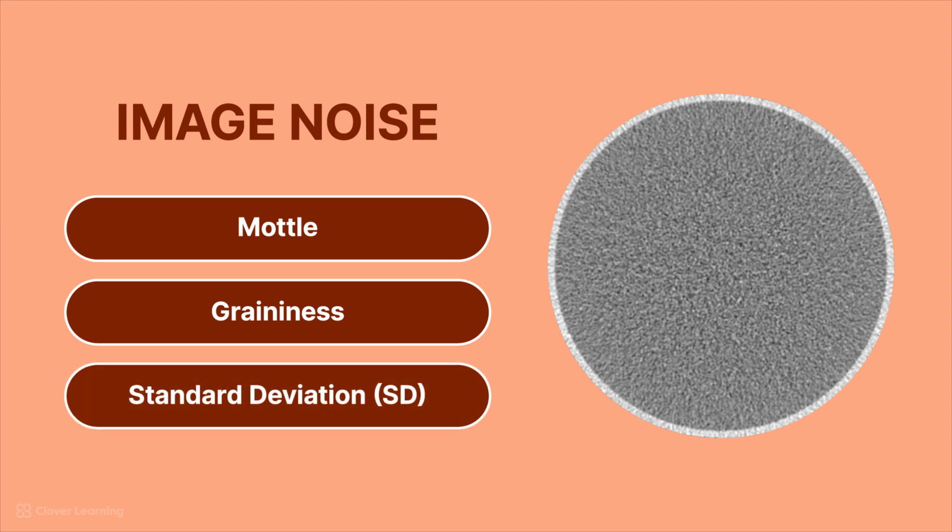All CT images have a certain amount of image noise, but we need to be able to measure that image noise to make sure nothing's wrong with the scanner. We measure image noise by evaluating the standard deviation using an ROI.